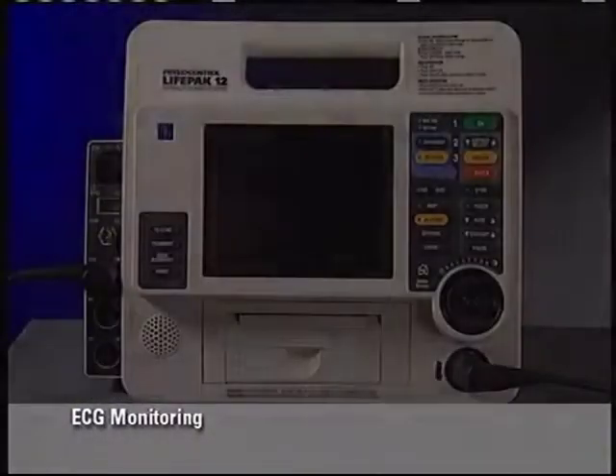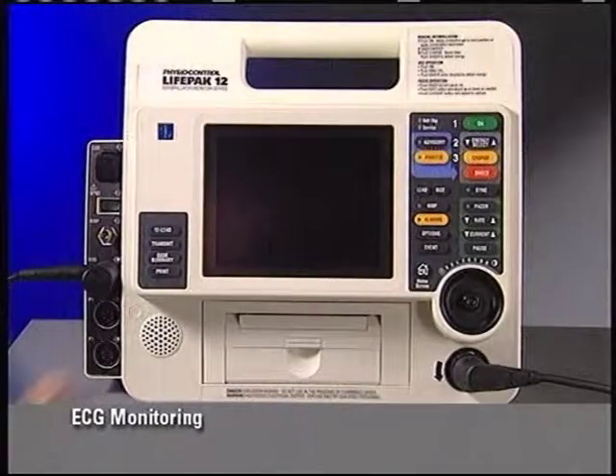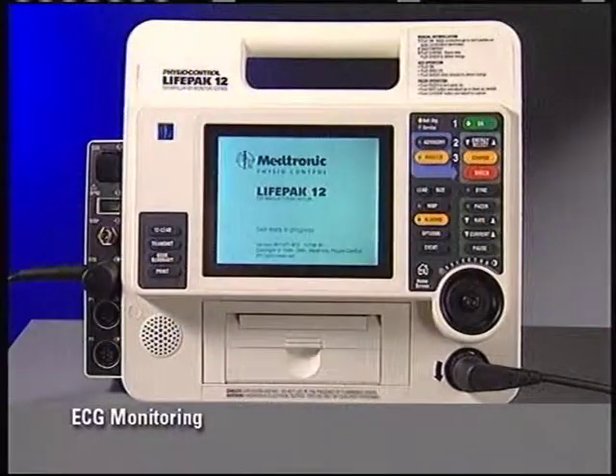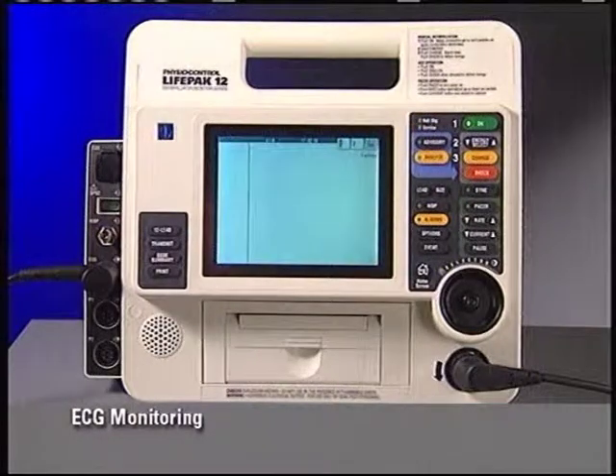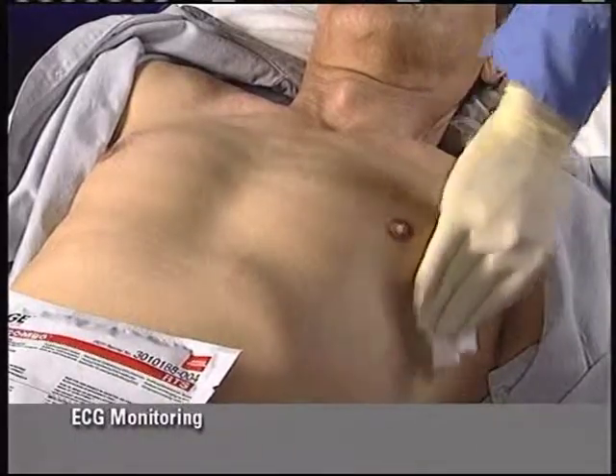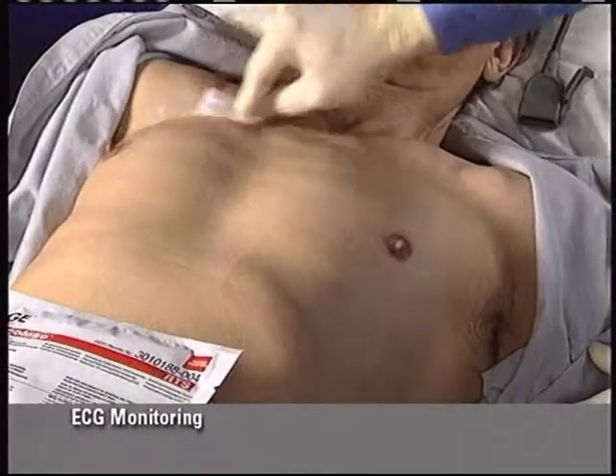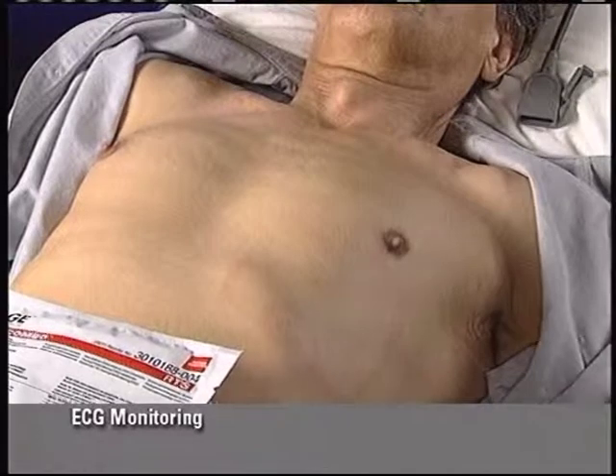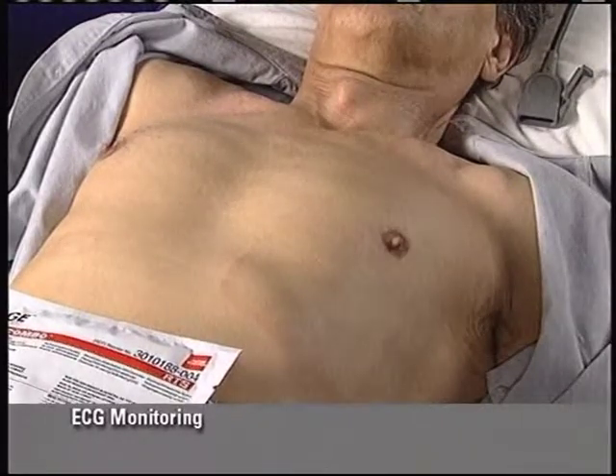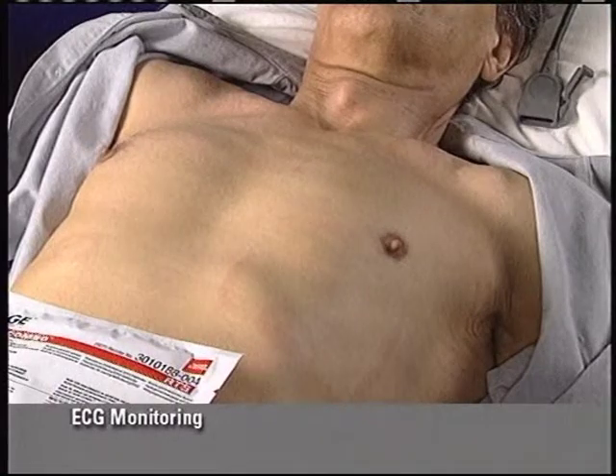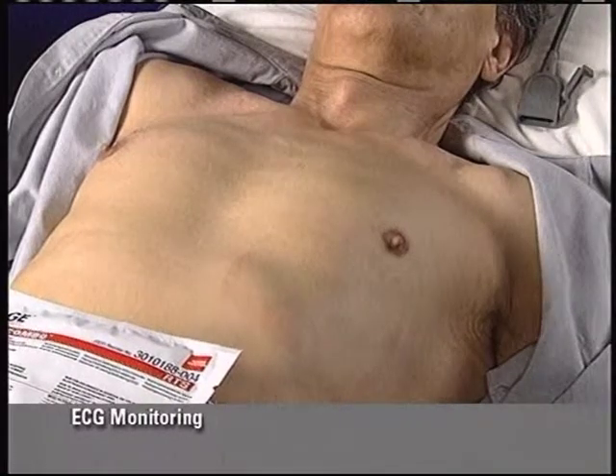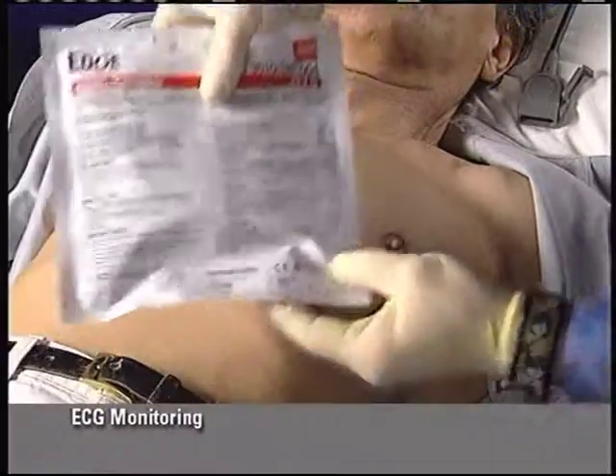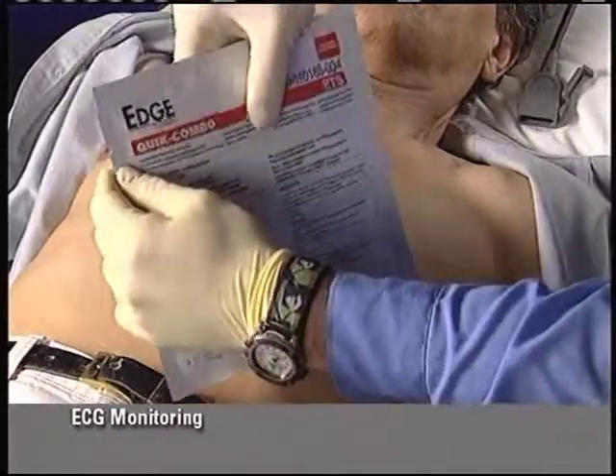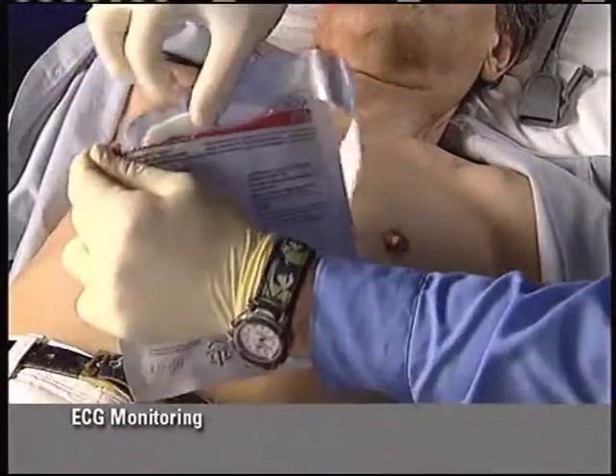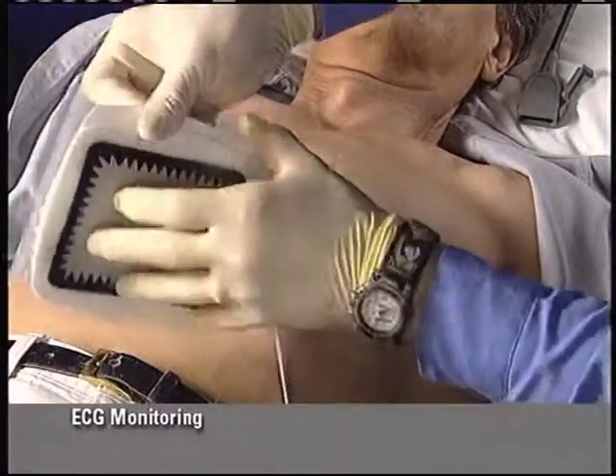To monitor the ECG in paddles lead with the quick combo therapy cable, press on, adjust screen contrast if necessary, connect the therapy cable to the monitor if not already connected. Wipe clean and dry the patient's skin, shave or clip excessive hair, and avoid placing electrodes over broken skin. Do not use alcohol, tincture of benzoin, or antiperspirant to prep the skin. Check that the therapy electrode's expiration date is not passed. To prevent drying out of the electrodes, open the package and remove the backing only immediately prior to use.